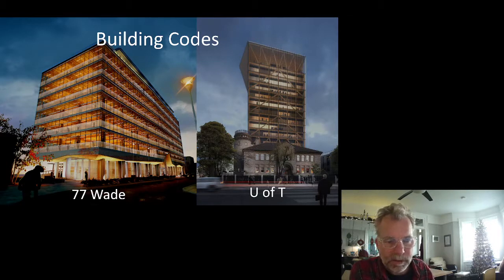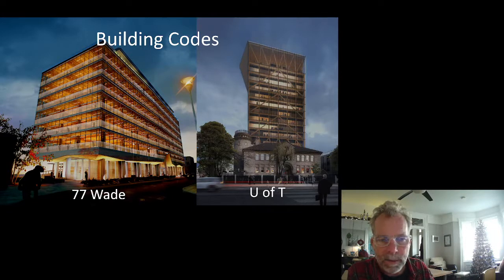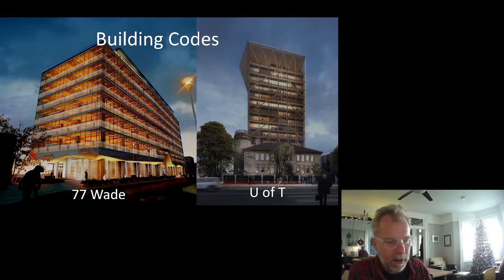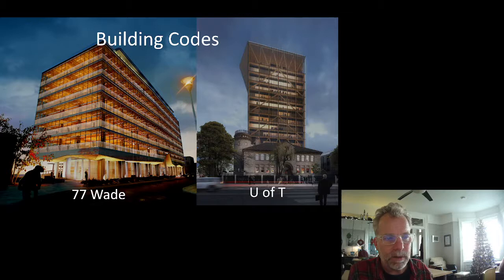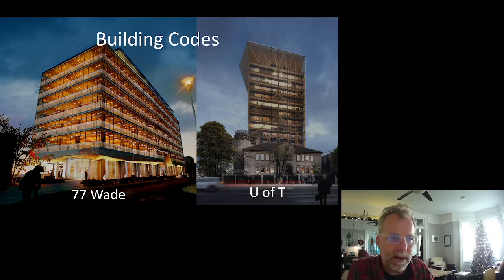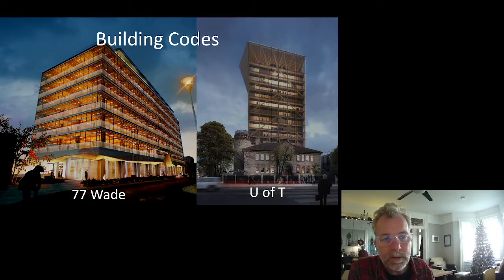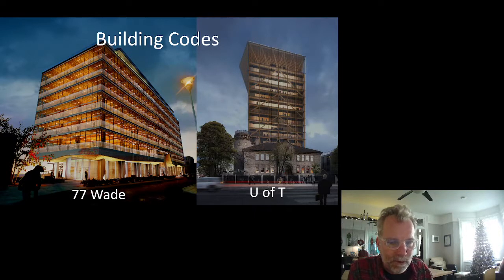Some of the things they do: you have a high fire rating — in a concrete building they might require one or one-and-a-half hour; at 77 Wade we have a two-hour fire rating between floors. You build your cores non-combustible — your vertical circulation elements are non-combustible. You pressurize your cores so you can't draw smoke into the core. You have an alternative water source for sprinklers to improve reliability. There are a whole lot of things we can do to demonstrate comparable performance.